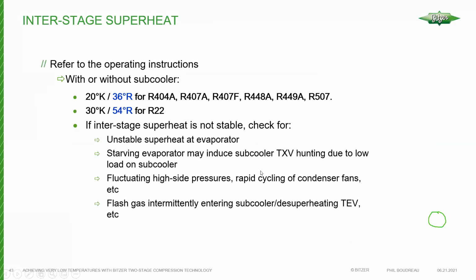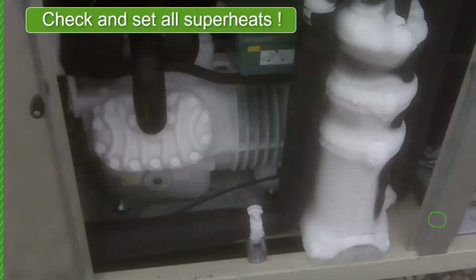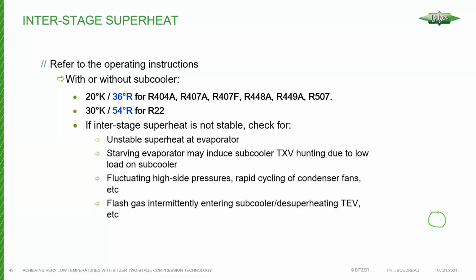Superheats, as always, are important. And yes, this is a two-stage compressor. As you take a look at that photo, our minimum crankcase temperature is 95, 100 degrees Fahrenheit or so. And in this case, you can see we're definitely not doing that. So in that case, minimum superheats for your interstage are 20 degrees Kelvin or 36 degrees R for most of the common refrigerants. With R22, which isn't really used anymore, it was 30 K or 54 degrees R. And I put some notes here.